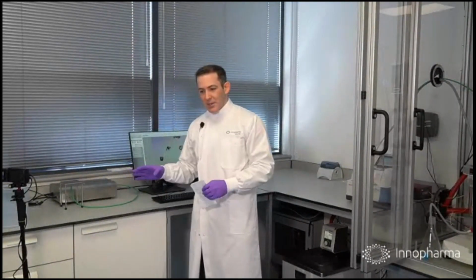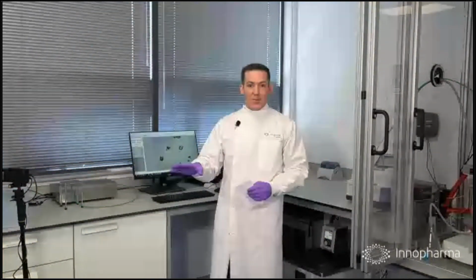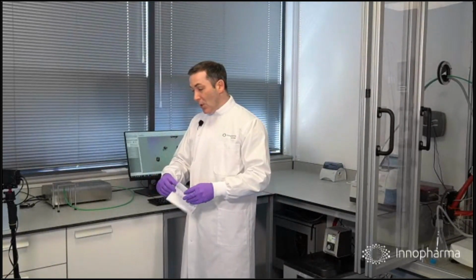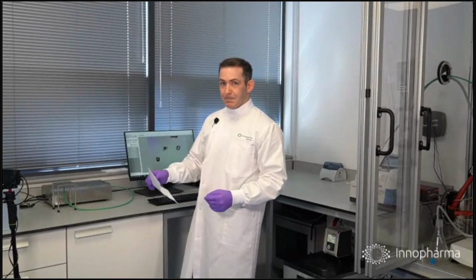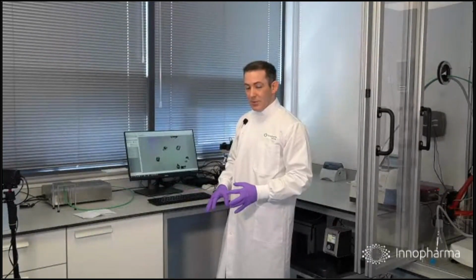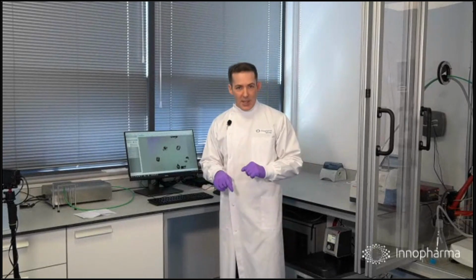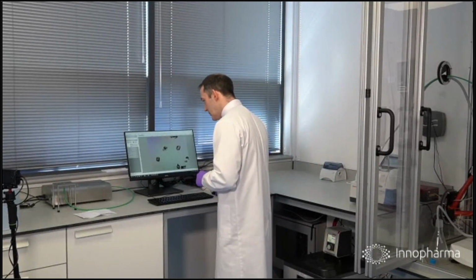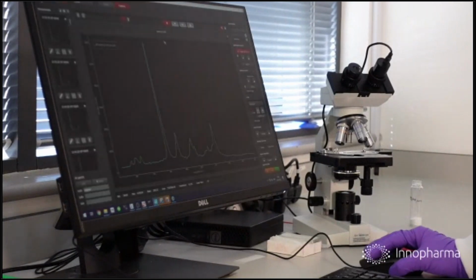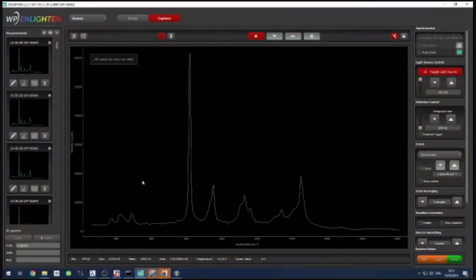So what we've seen is the consequence of allowing the reaction to proceed in an uncontrolled way. And I hope that alone is enough to justify controlling the reaction, controlling things slowly. But what we would really need is a method, as I said, of looking into the process to see how it's happening and how it's progressing in real time. So for that, we need to look at the sensor data. So I'm going to switch back again to show you what the sensors are seeing at the moment. We'll see what the Raman sensor is seeing, and it sees a spectrum.